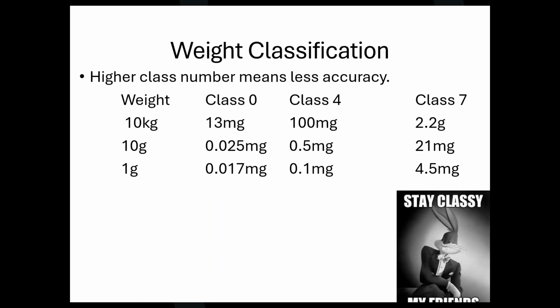All right, we're talking about accuracy here. Now, in the calibration metrology world, when we come on site to do your calibrations, we have to have something that is 4 times more accurate, that I'm testing with, than whatever I'm testing. So, easy number here, if you've got 4% tolerance on this device, I have to have 1% or better. We'll talk about this a little bit more as we go on. Now for you guys, you really don't have to go to that extreme. Typically what I see, if you can at least get 2 to 3 times greater accuracy than what you're measuring, you're going to be okay.